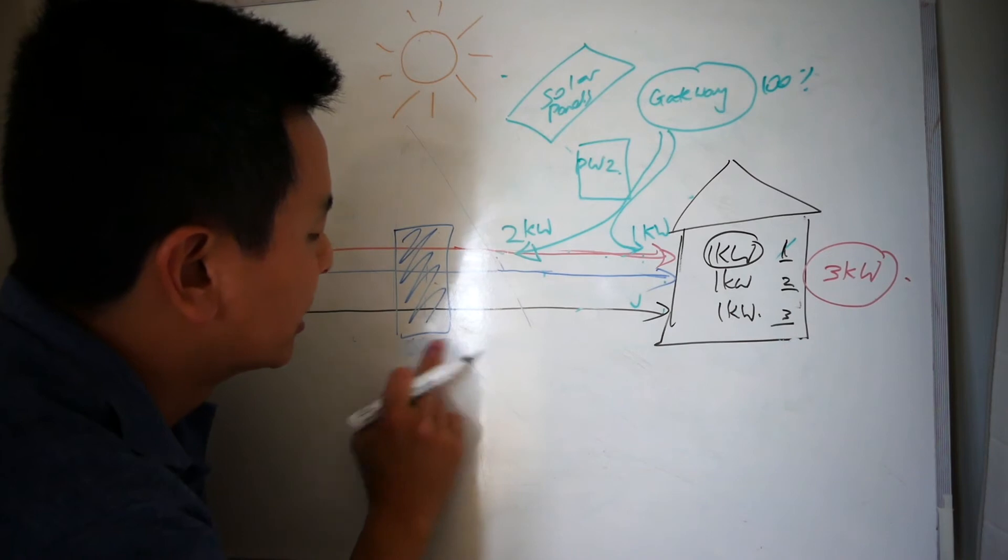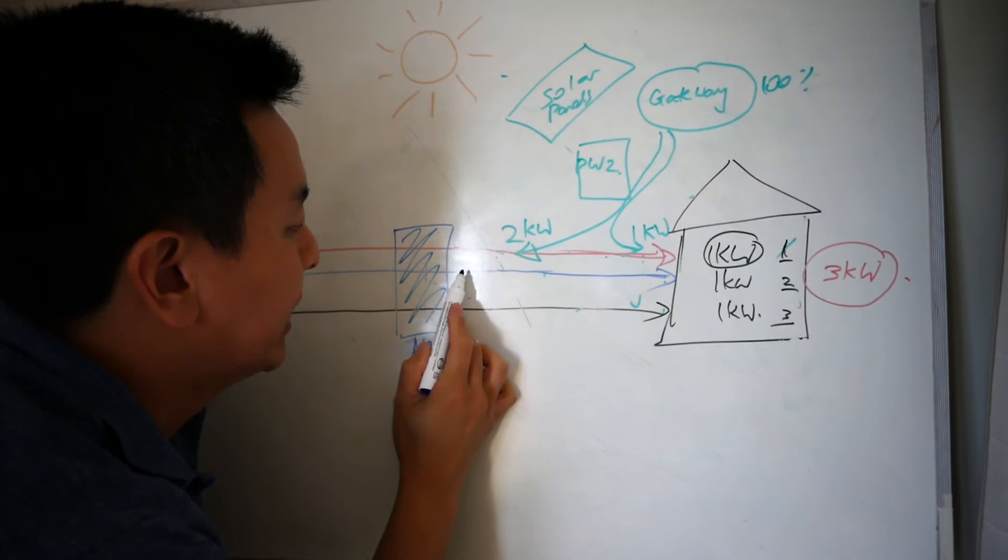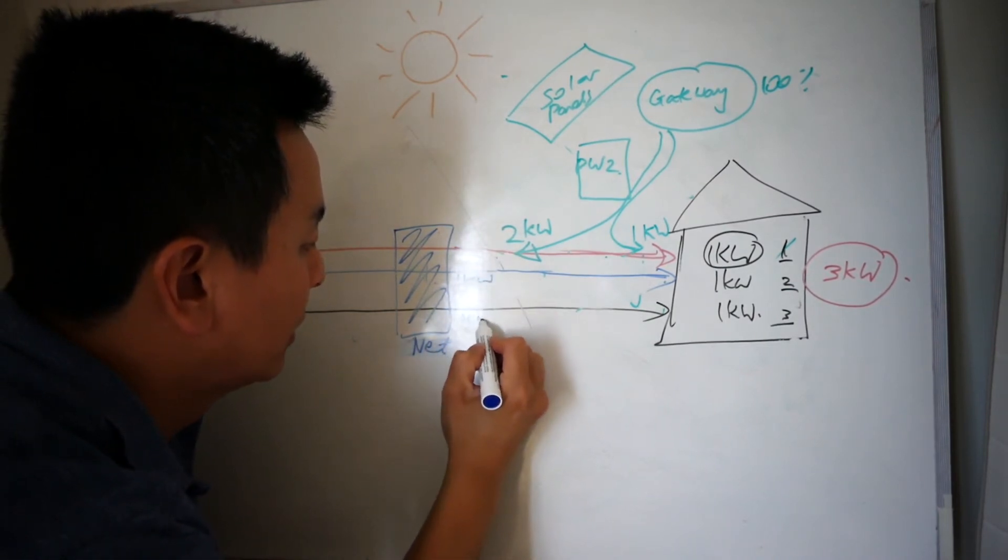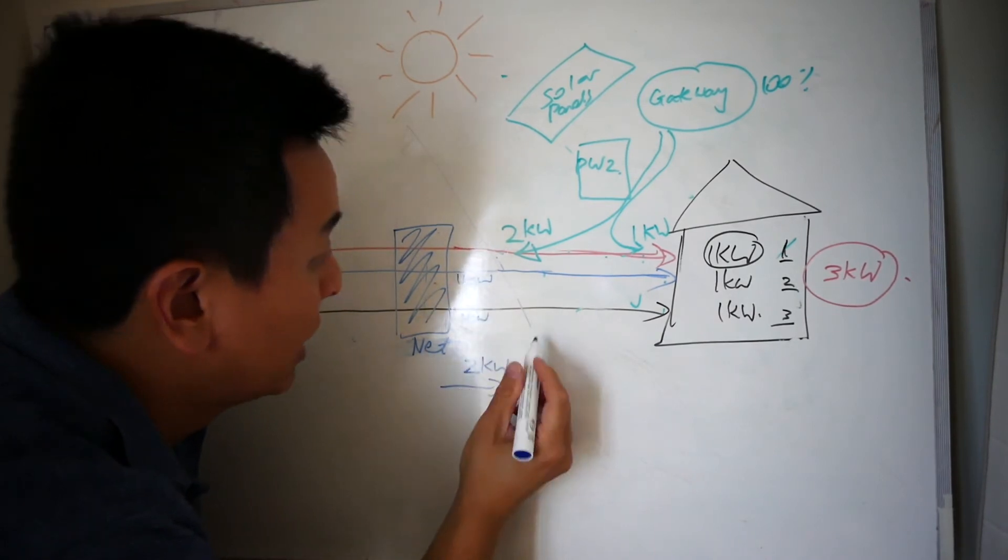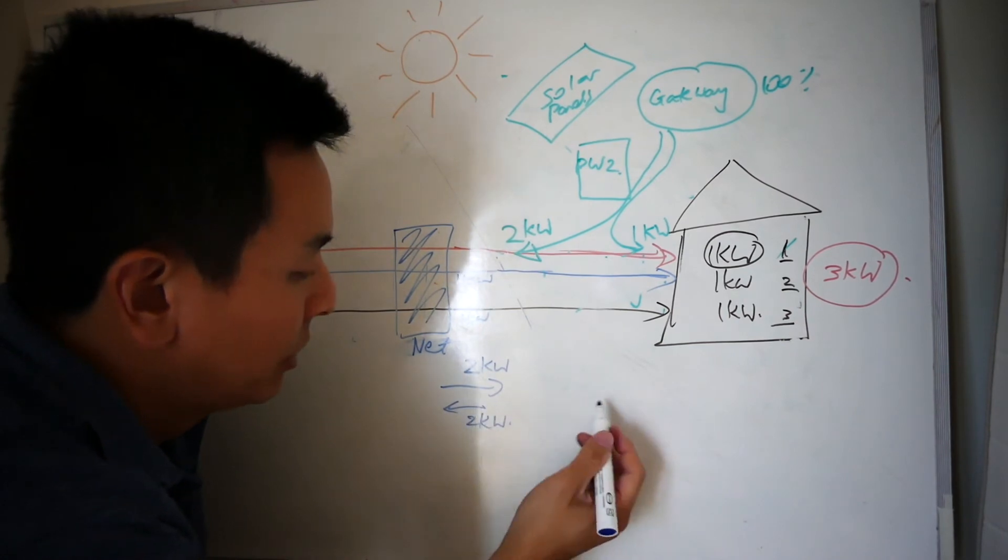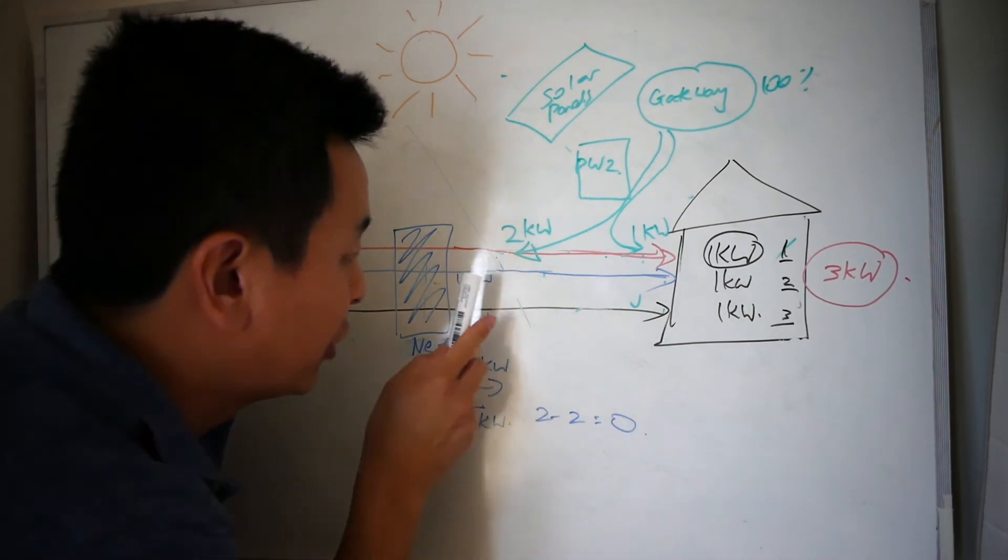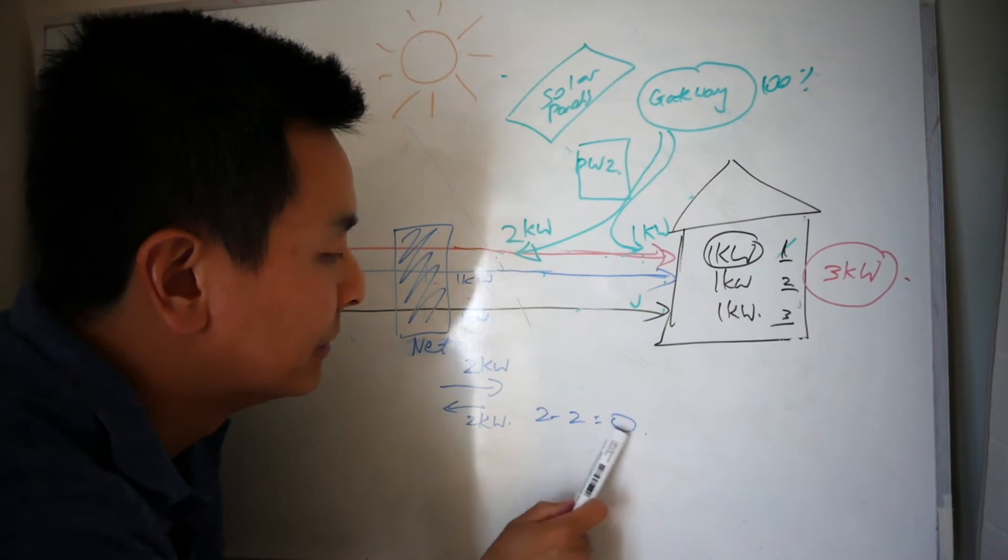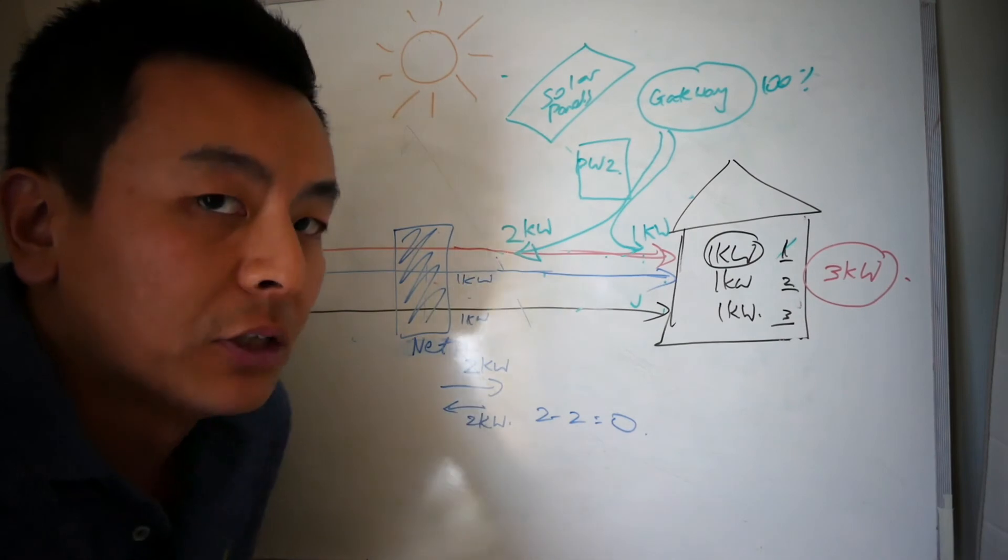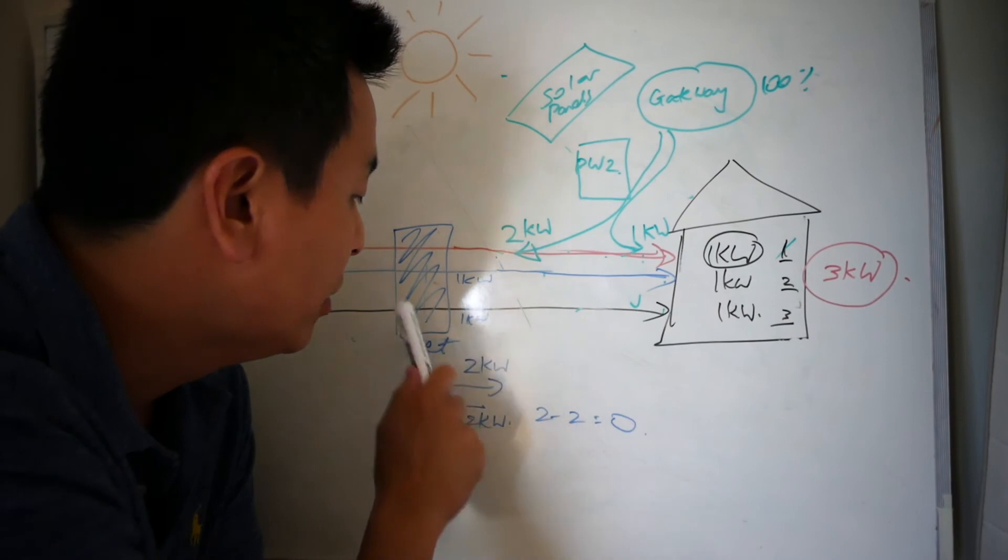So the net meter does this. So on these two phases here, on the blue phase and the black phase, it's supplying one kilowatt. So there's two kilowatts going this way, but there's also two kilowatts going back this way from the Powerwall 2. Two minus two, zero. So effectively, even though electricity is coming from here, on your bill, it'll be zero because the net meter goes, okay, two minus two, two going this way, two going back this way. Let's not bill this customer at all. So that's how the gateway works with a three-phase home with a net meter. Obviously that's not going to work with a gross meter. It just wouldn't work. You'd just be paying too much. You'd be paying for the grid usage and then getting a crappy feed-in tariff, which means you'll be getting charged for electricity, which has been covered already by the Powerwall 2.